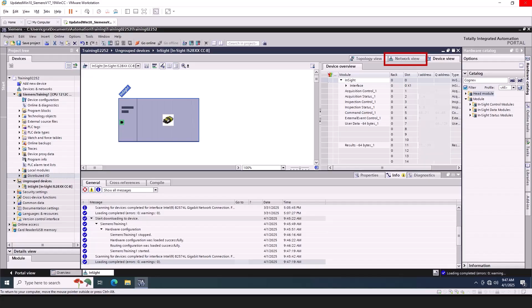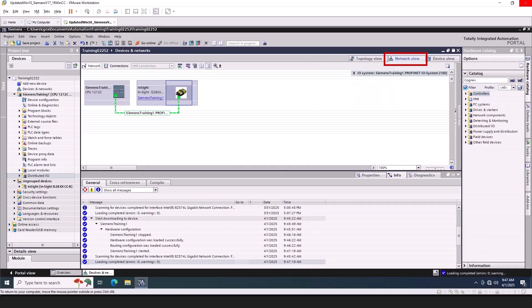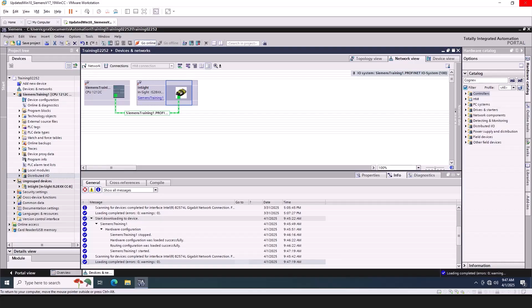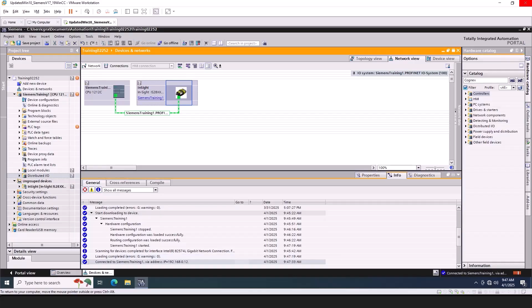Return to the Network View tab. Click the Go Online button. Notice everything in the Project Tree and the Device Overview tab are green. This means that the PLC is communicating correctly with the camera over PROFINET. Click the Go Offline button.